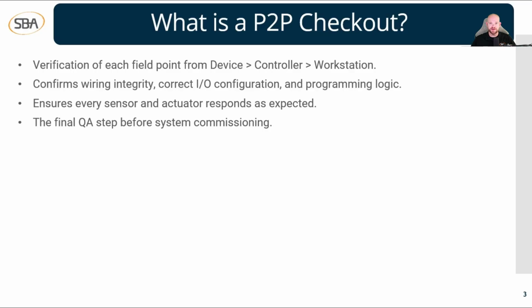We have to verify all these things, and that's the whole idea with a point-to-point checkout. The last thing for this second point is that we also check any programming logic that we've already built out. So that confirms our wiring integrity, our I/O configs, and our programming logic. Then we go down to the third point. Point-to-point checkout also ensures that every sensor and actuator responds as expected. This makes sure that everything's operating how it's supposed to: we have good values from our inputs, and our output commands are operating as they should.